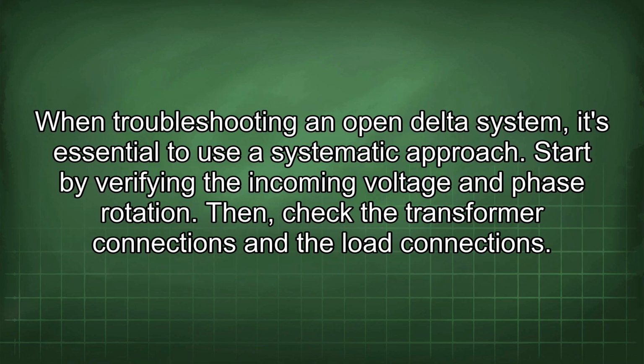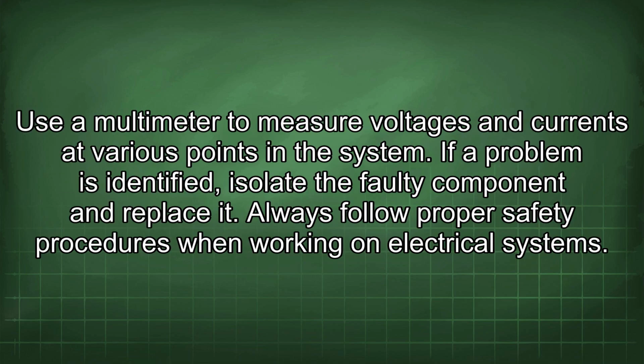When troubleshooting an open delta system, it's essential to use a systematic approach. Start by verifying the incoming voltage and phase rotation. Then check the transformer connections and the load connections. Use a multimeter to measure voltages and currents at various points in the system. If a problem is identified, isolate the faulty component and replace it.